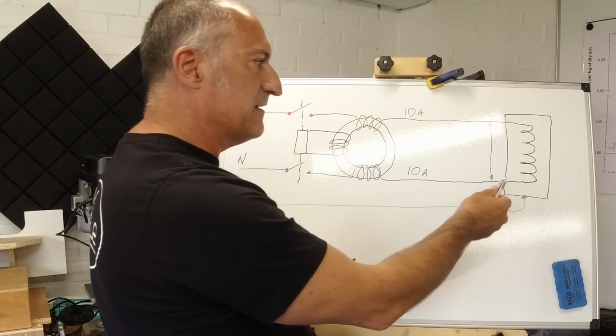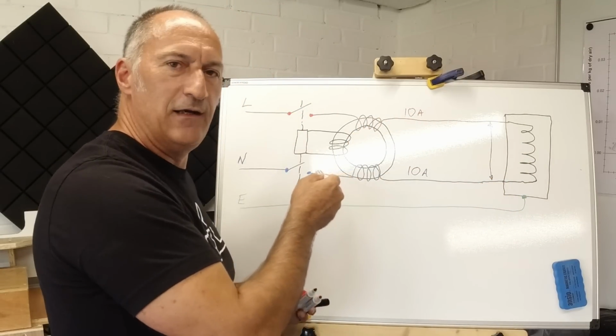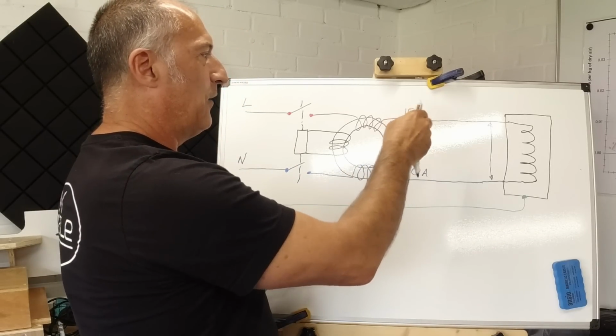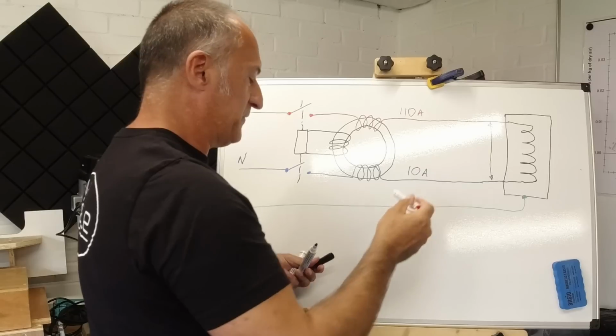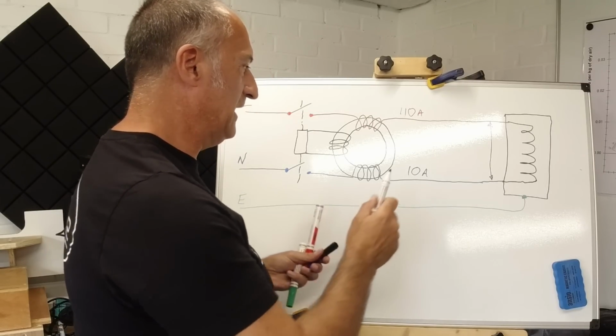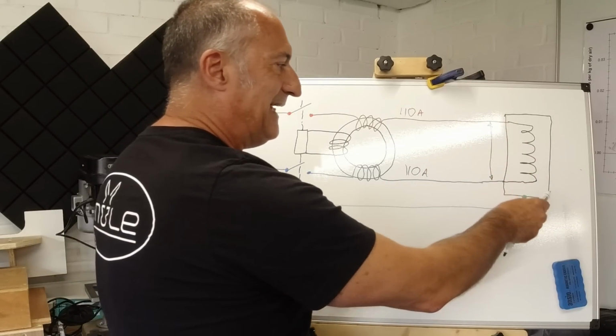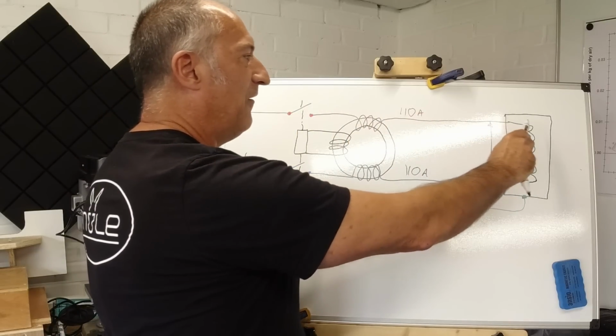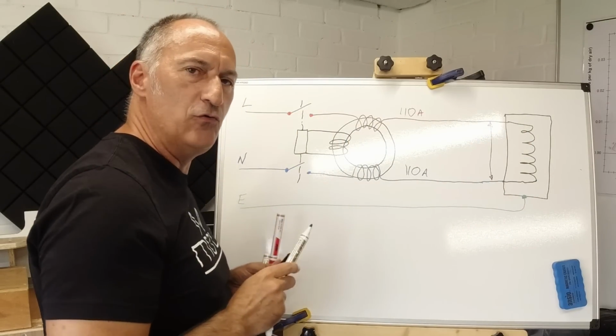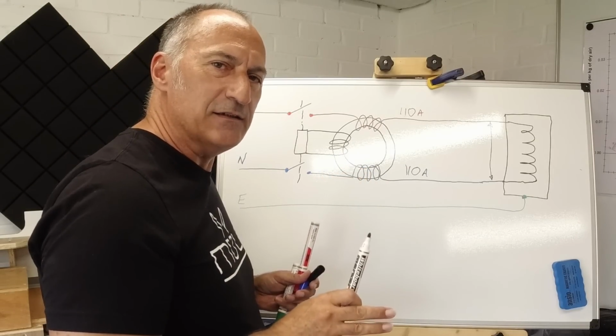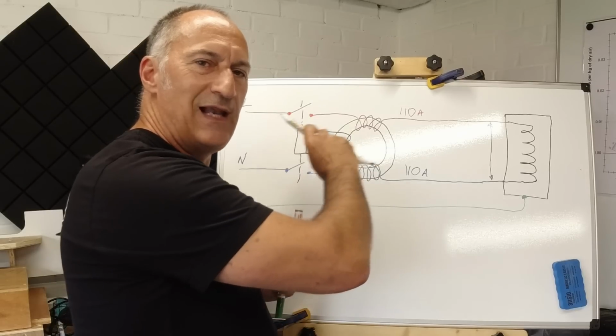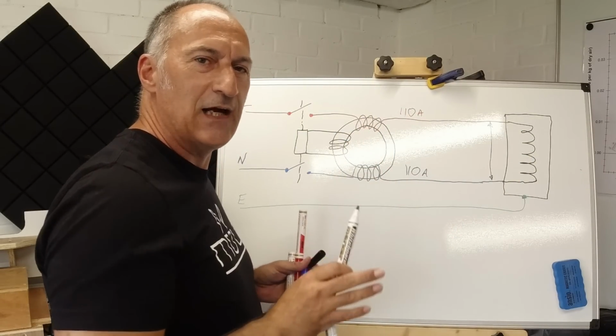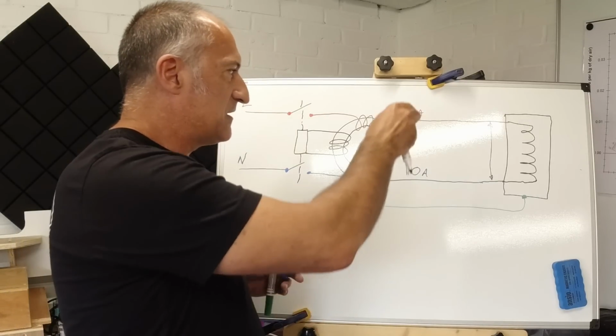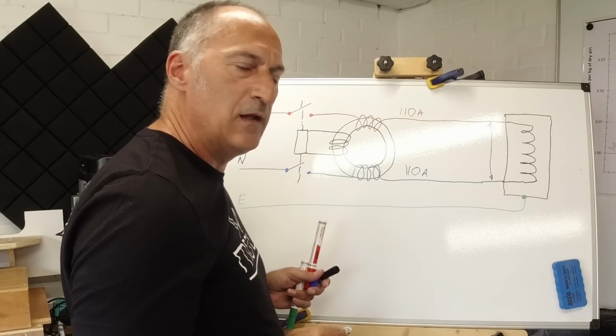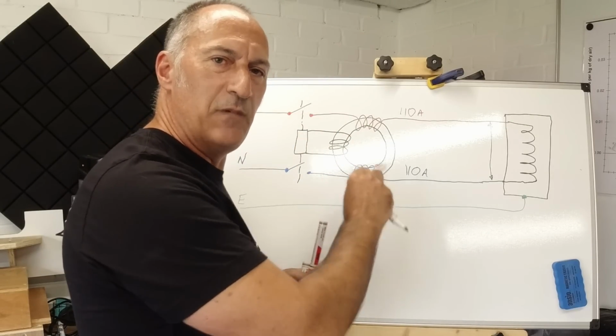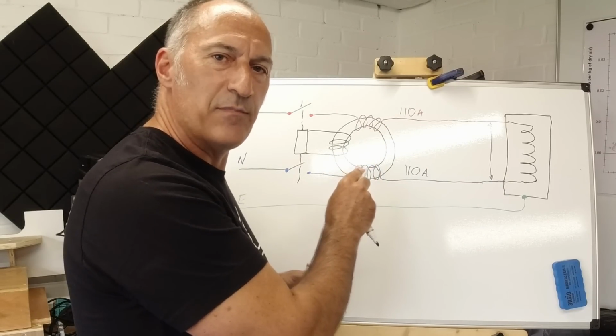Instantly, because you haven't got this resistance, there's going to be a huge surge in current flowing around the circuit. So these values of current are going to go up massively. Let's just say, up to 110 amps or even more instantaneously. But because nothing's leaking back down the earth, what's going down the line is the same as what's coming back on the neutral. So this RCD is still in balance. So this is not actually going to trip. It's going to allow all that current to flow down the circuit, and it's going to sit there quite happy. It doesn't see a fault in this case because there's not an imbalance across the line and neutral. So we need another device to protect us from overcurrent because the RCD is not going to give us that protection.